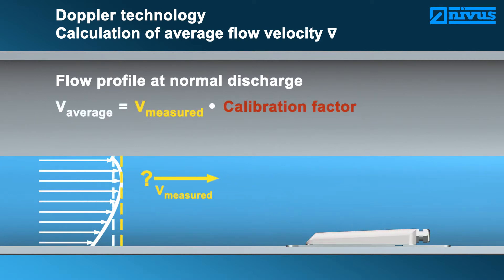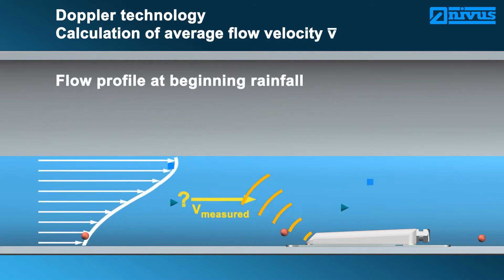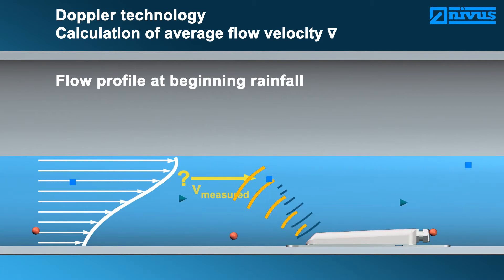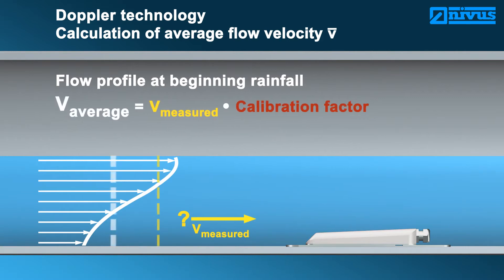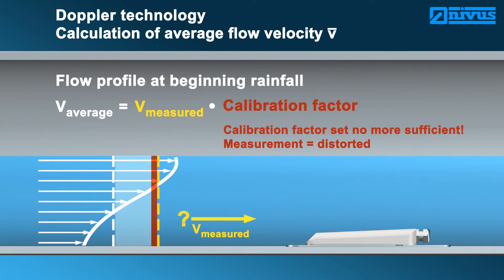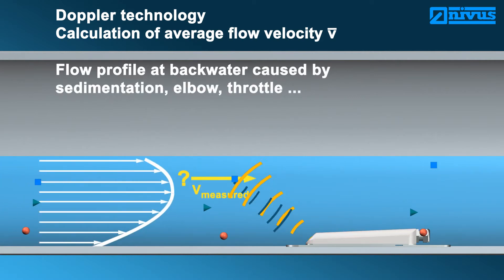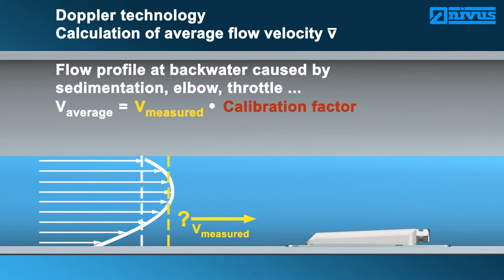To counteract this shortcoming, the average flow velocity is computed with the aid of a calibration factor. This factor must be determined previously, such as by implementing a grid measurement, which is fairly time consuming and expensive. The calibration factor is valid only for one stationary condition. If the flow conditions should change, such as due to rainfall, the flow profile will change accordingly. The originally determined calibration factor hence is no longer applicable and the reading is distorted. The flow conditions will also change in case of backwater formation caused by sedimentation, elbows or throttle equipment, making the original calibration factor no longer valid.